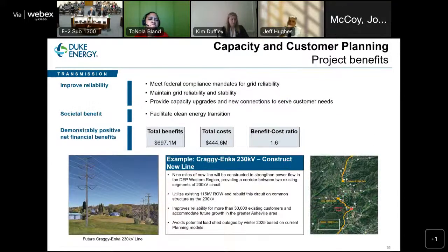One specific project location I'd like to discuss is the Craggy-Enka capacity project. On the picture on the right side, the north and south parts represent the general Asheville area. You can see the yellow line, that's an existing 230 kV transmission circuit. Conspicuously in the middle, there is no 230 kV circuit between the Craggy and the Enka substation. So we're missing this corridor in the central Asheville area, or to the west side, where we are limited in how much power we can transmit between the different parts of the system.